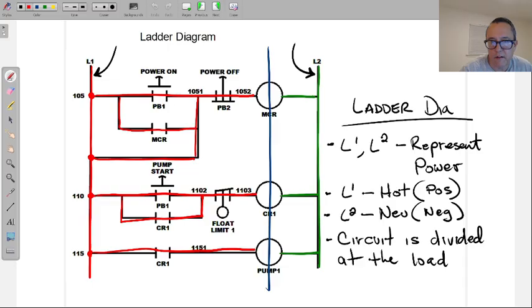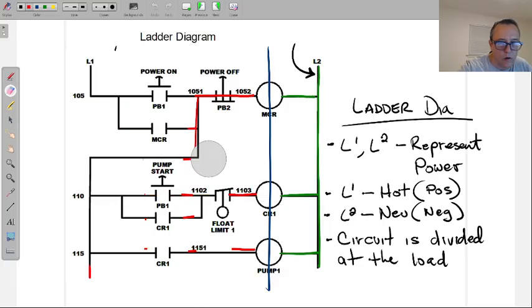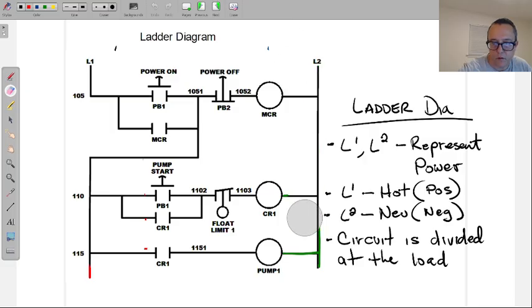Heading back over to the diagram I had here. Okay, check, L1 and L2 have power. Now if this pump is not working, well, something along the line has not engaged to provide power to the rest of things. And that's all troubleshooting in motor control is. It's follow, point to point, for those of you who did Code D with me - point to point checking.